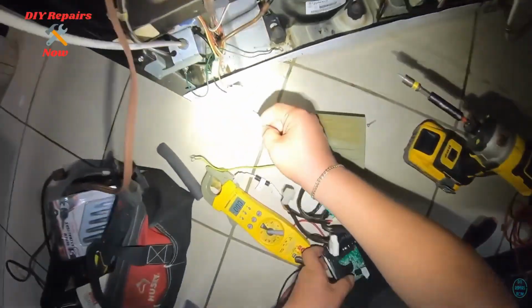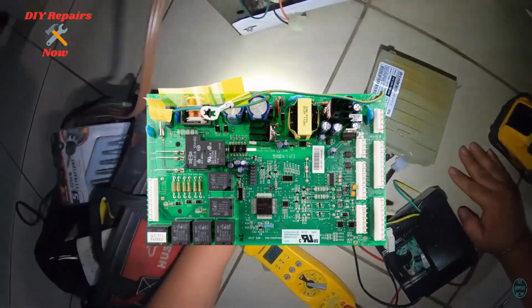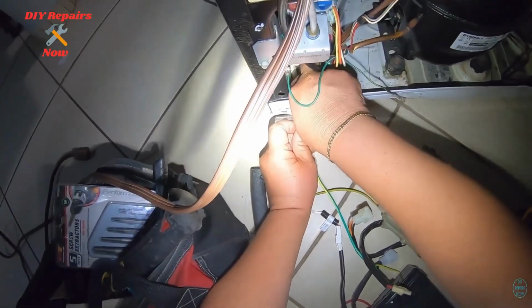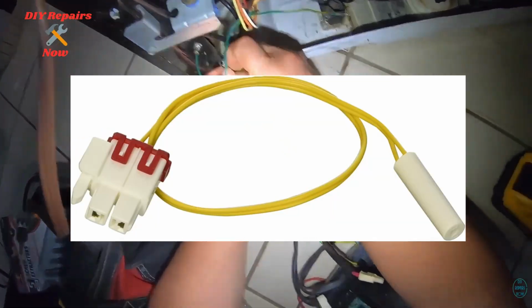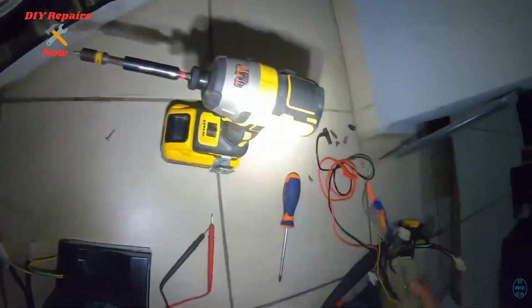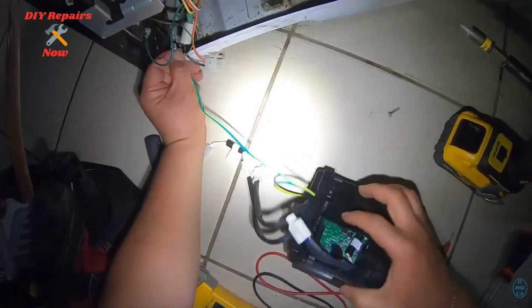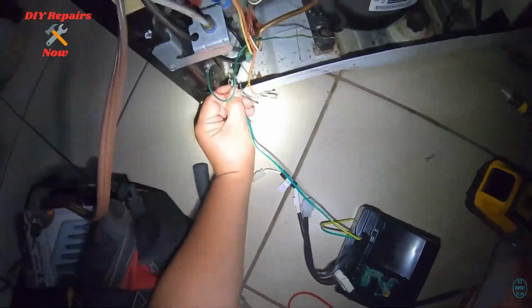A no cooling problem can also be caused by a failed compressor, a problem with the main control board, wiring or connector problems, a communication problem, a temperature sensor problem, a power supply problem, a sealed system problem, or another component in the refrigerator. That's why you need to test the system instead of replacing parts based only on symptoms.